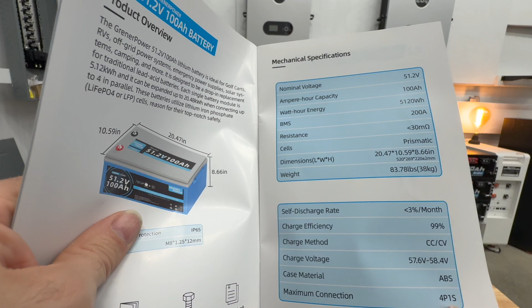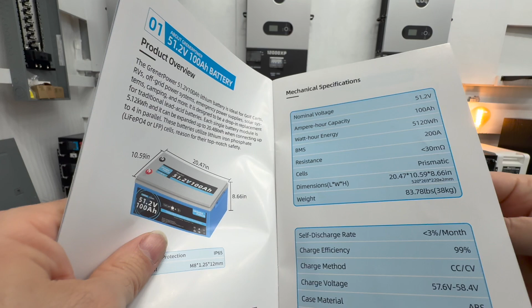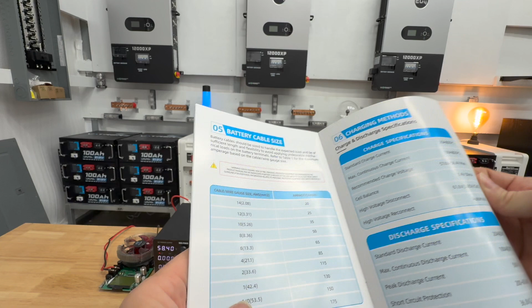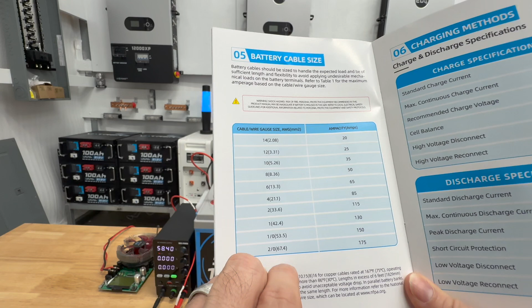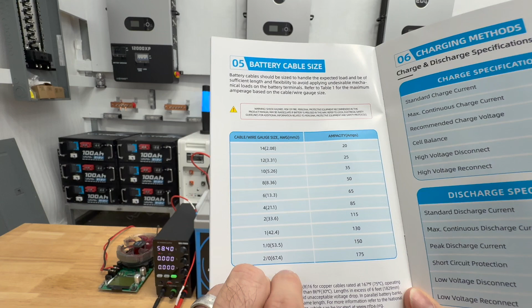Once this is fully tested, I am going to take this battery and throw it on my shop setup, which already has 12 in parallel, so this will be lucky 13. Few things in here. It talks about wire gauge, really important. So you're going to fuse for the wire gauge that you have. I recommend using T-class fuses on all 48 volt batteries.